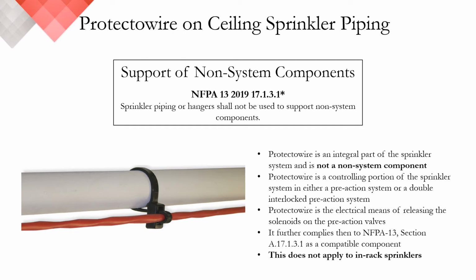Sprinkler system hangers are designed to support 5 times the weight of the water-filled pipes, plus 250 pounds at each point of pipe support. Considering the weight of a 500-foot, about 150-meter length of Protectowire linear heat detector weighs 8 pounds, or just under 4 kilos, this has a negligible loading effect when the detector is supported by the sprinkler piping. I want to be clear, though, that pipe mounting to in-rack sprinklers is not recommended. Regardless of everything we've said here so far regarding NFPA 13, always seek approval from your local AHJ prior to any designs or starting installation.